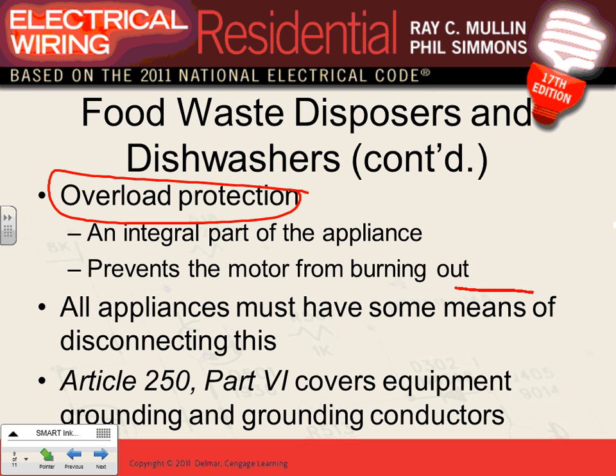And the appliances have to have a means of a disconnect. We talked about this one. Grounding: all you need to remember is when you ground equipment, guys, each one of these appliances has to have an equipment grounding conductor.